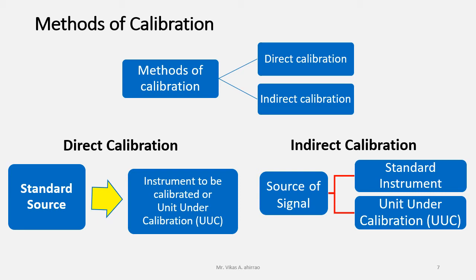For example, if we want to calibrate a pressure gauge, then we may have the pneumatic supply, that is the air supply, as a source of signal that will be simultaneously fed to the unit under calibration and a standard pressure gauge. Then the reading shown by the standard pressure gauge and the unit under calibration will be compared.